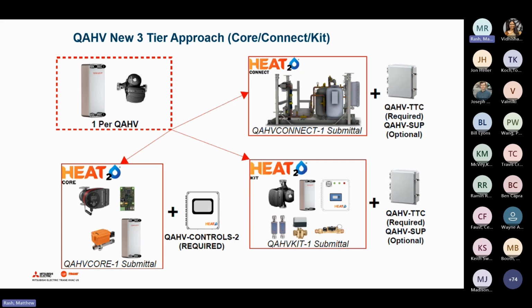So this is not a return to primary. I know that question came up. Again, this is high delta T. It's a single pass application. We want to see this applied with series type storage tank arrangements, as you see here in this basic diagram. So there always has to be a separate swing tank to handle those idle loads, those low delta T loads. And again, the series tank configuration maintains the stratification and maintains our water temp, both as it charges and as it discharges. So again, it's geared for high delta T operation.